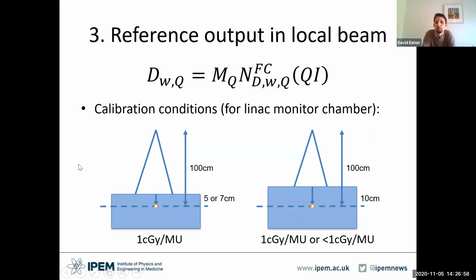Now, one area where we have gone beyond the 1990 code is to recommend certain calibration conditions, as these relate to your LINAC monitor chamber. So you might not just measure the dose, but you might actually adjust the output of your LINAC to give a certain dose in a certain setup. And then we recognize that there are different practices and there have been changes in terms of historical practice. So in the past, many treatments were delivered with a fixed SSD approach, so 100 centimeters to the surface. And so it was typical to calibrate your machine with 100 centimeters to the surface of your block or your water phantom.